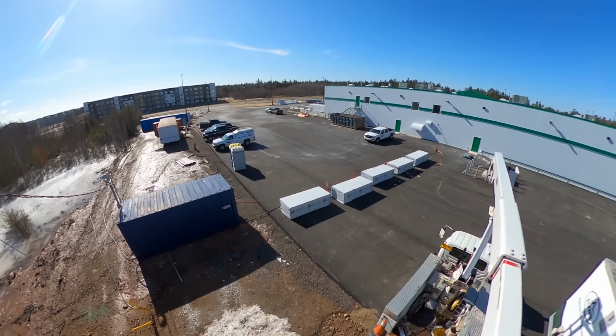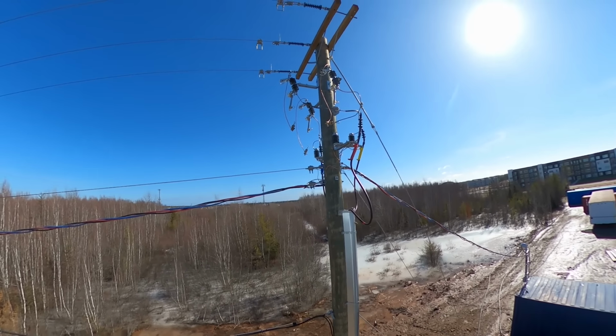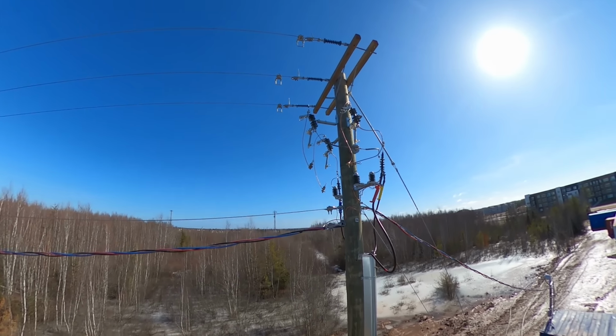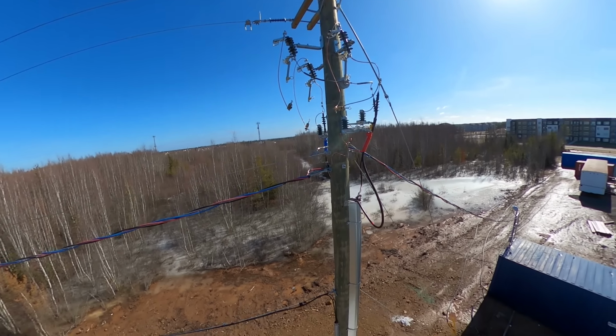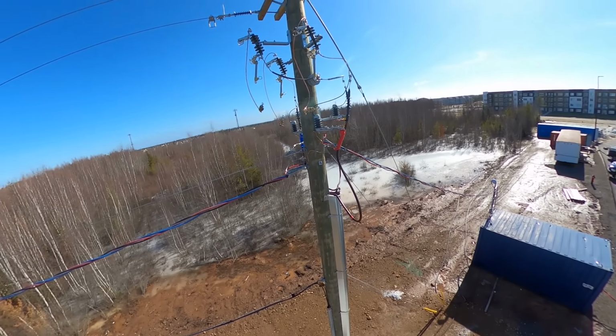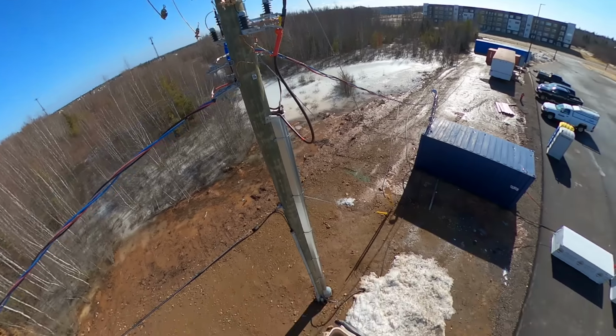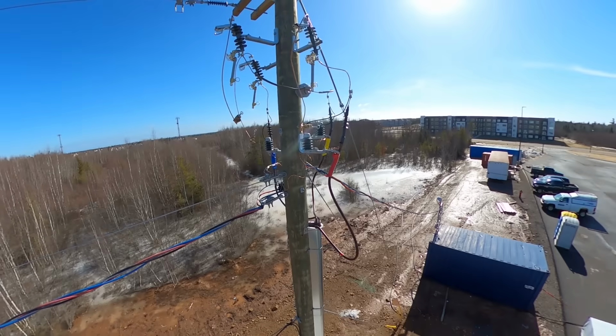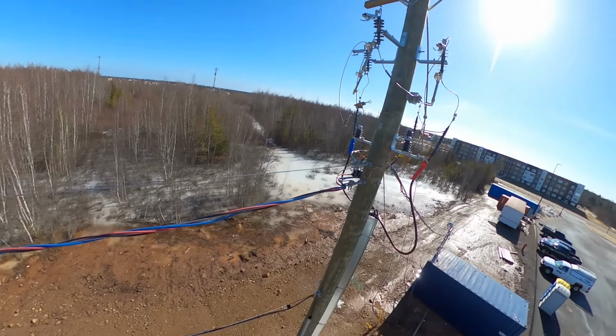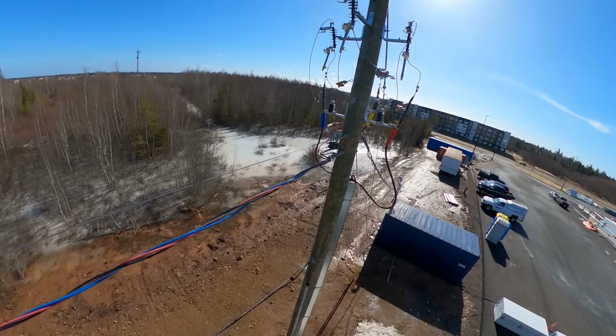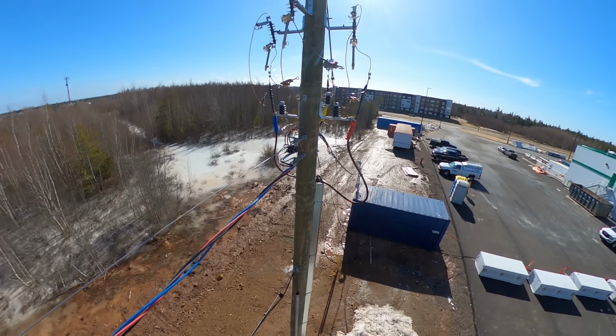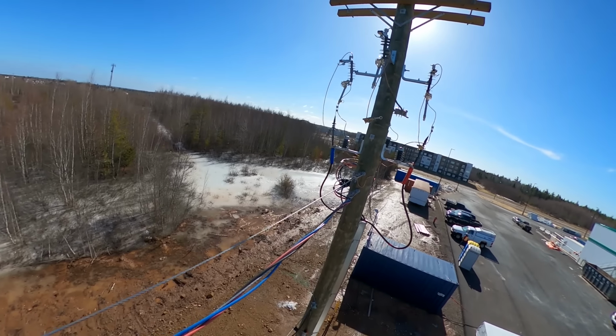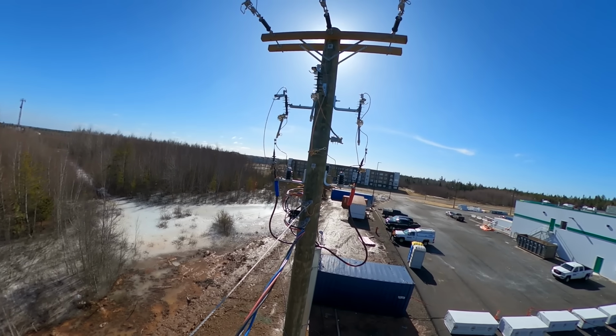So like any job, as we're approaching the pole, we're taking a look at everything. As my boom slowly gets closer, I'm looking at that pole from top to bottom. I'm not too concerned about failed equipment or cracked insulators where it's brand new. I'm just double checking the guy's work, making sure everything's tied in properly, and trying to line up that pole with the sun so I can actually see what I'm looking at here.